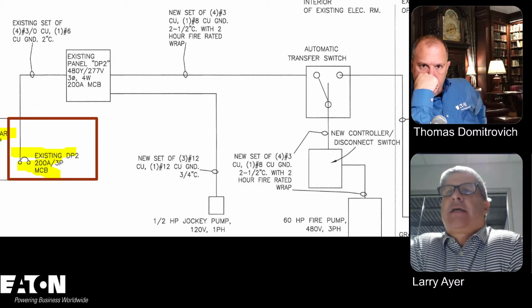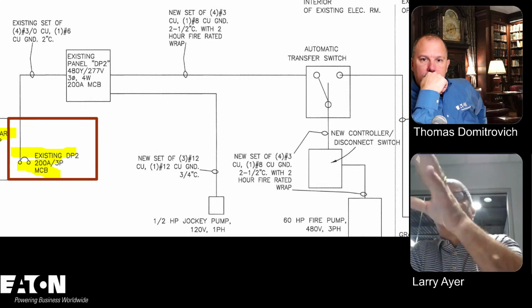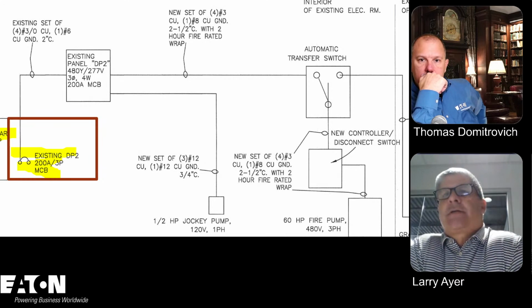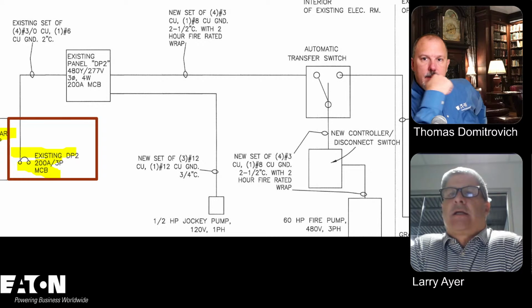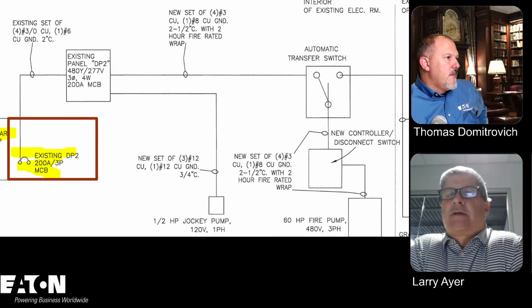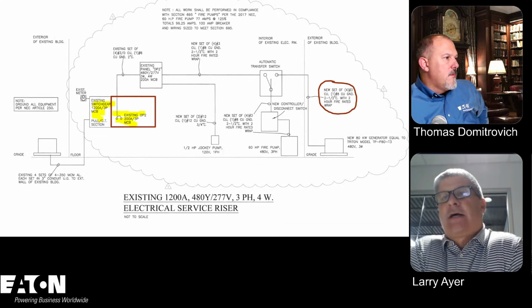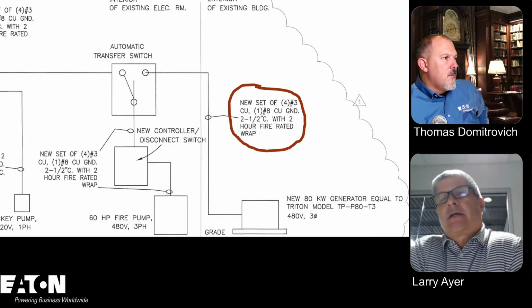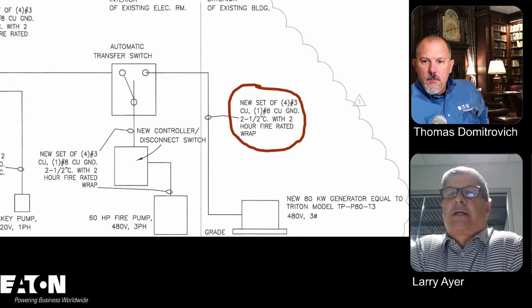So he's got his wires set up there, and he's got a 2-hour fire rated wrap to go to the transfer switch, and he's got his 2 hours over there for the genset. So he's doing something right, but, and this is important, there's a lot of code rules that go into this, and it's important to review the NFPA 20 and the 695, and get some help on it to make sure we do this right.